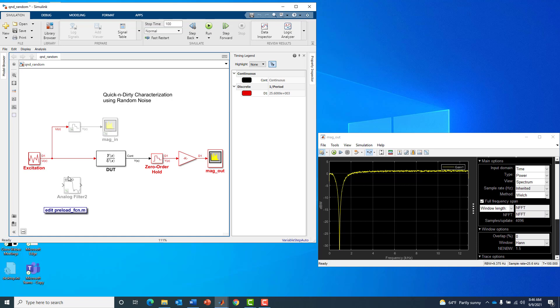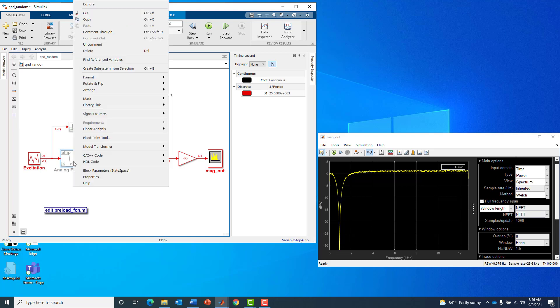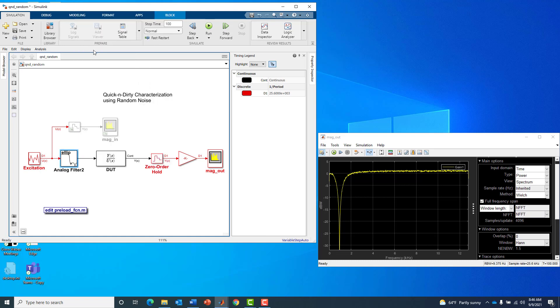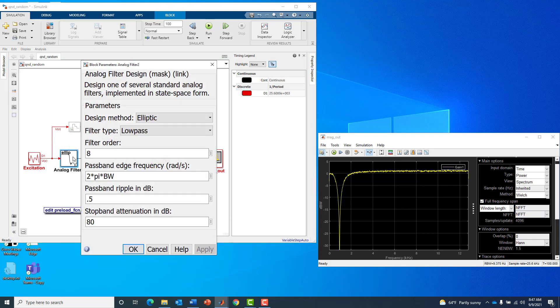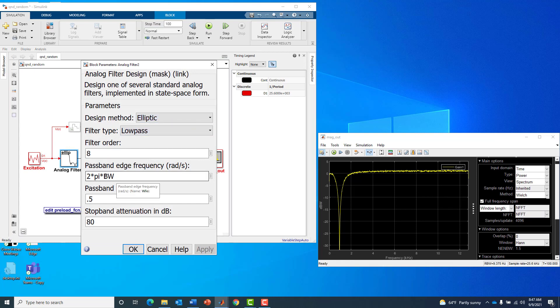That's very high frequency. So we would like to remove those higher frequency components as seen by our device under test. I'm going to uncomment this anti-alias filter, which is elliptic low pass eighth order with a bandwidth of 10 kHz.